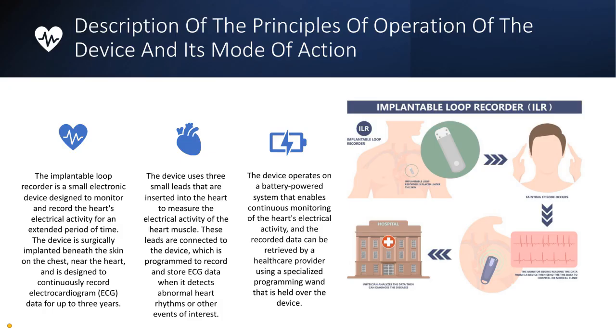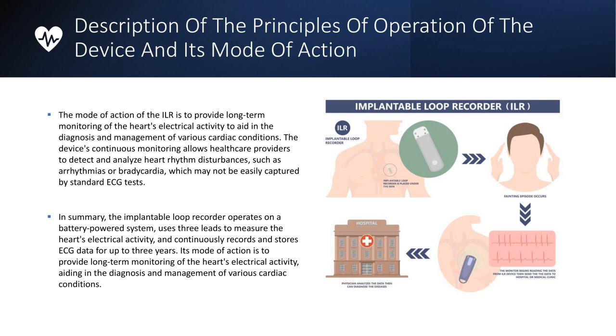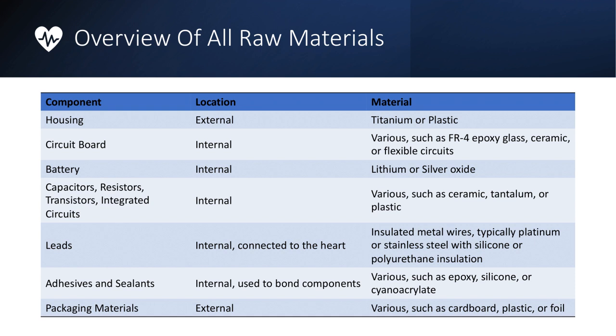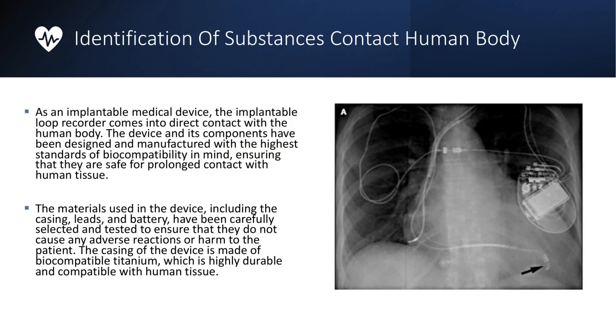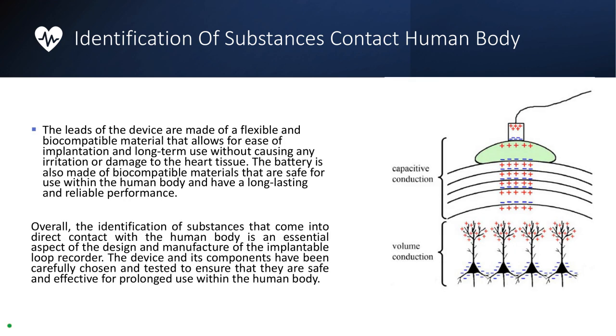The device is surgically implanted in the chest, close to the heart, and designed to continuously record ECG data for up to 3 years when it detects abnormal heart rhythms. The mode of action of the ILR is to provide long-term monitoring of the heart's electrical activity to aid in the diagnosis and management of various cardiac conditions. In the overview of a raw material table, we see that it is examined according to component location and material. It comes into direct contact with the human body, so the highest biocompatibility standards are taken into account and it is made of titanium. The leads of the device are made of flexible and biocompatible material that ensure ease of implantation and long-term use without causing any erosion or damage to heart tissue.